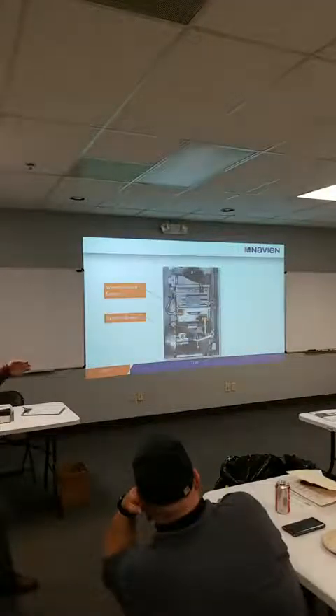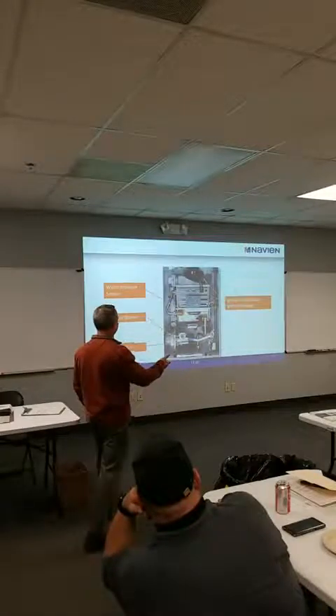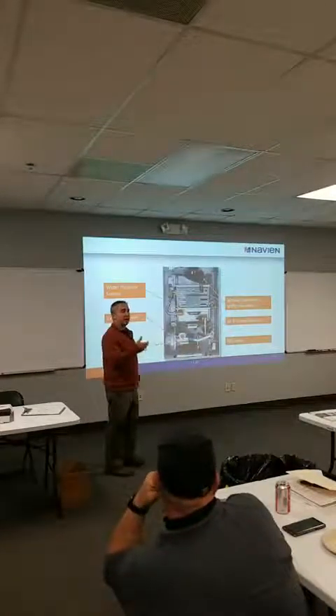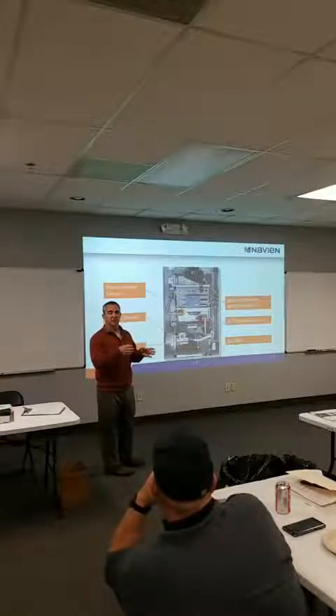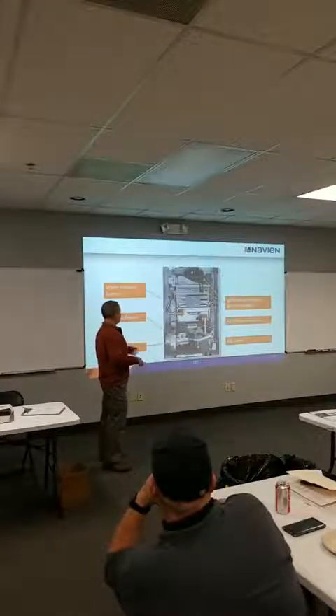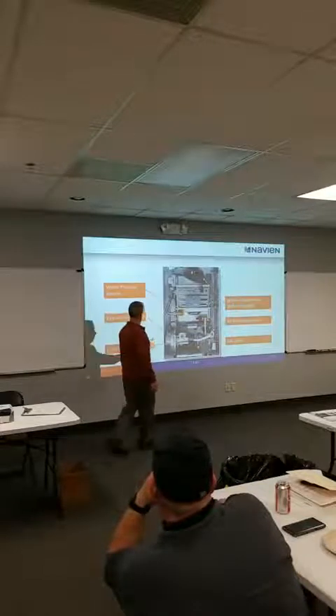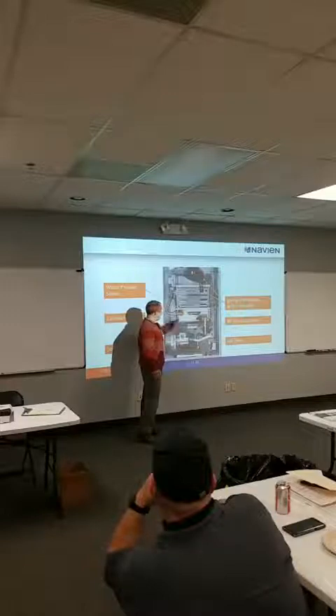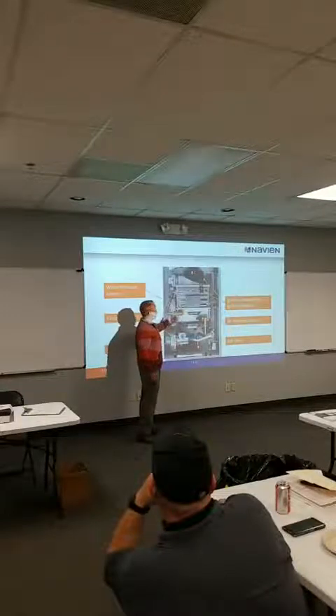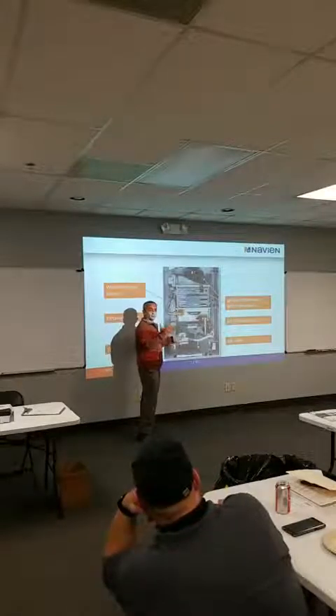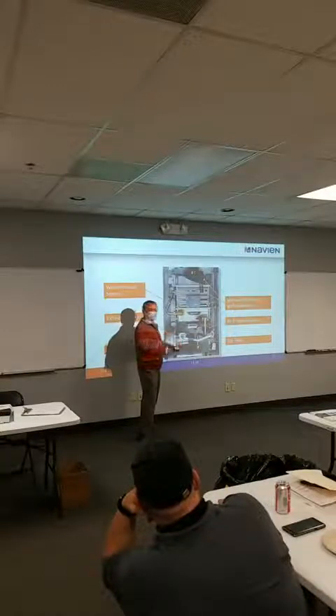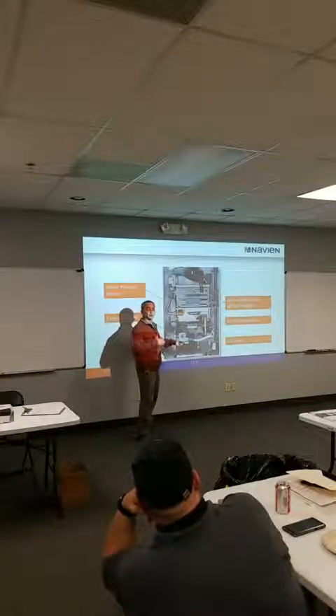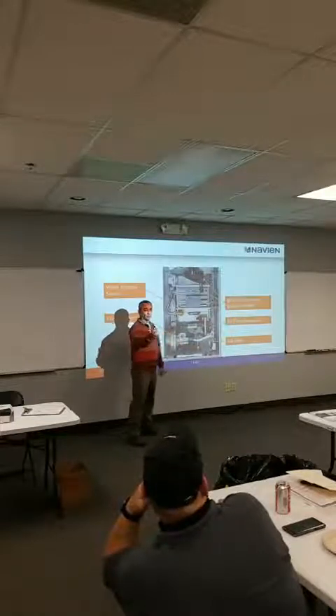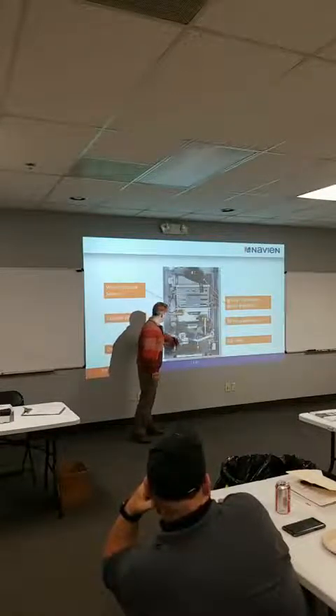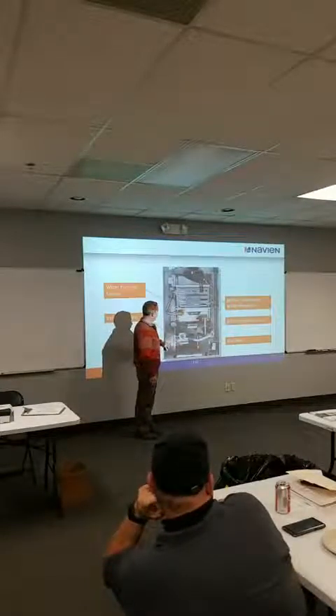The setup of all the equipment is going to be a little different, but the internal parts are basically the same. We just move them around based on either the heat exchanger that we're using or how much stuff we have to put in that box. So you're always going to have an inducer. You'll see our inducer draws air into the cabinet itself. When the cover's on, we're drawing air into the intake, which is protected by a screen. With the cover off, you're just drawing makeup air, which all of our units are approved for. So if you ever get to a job and the cover is off, anything that's in that cabinet or that room, we're actually drawing into the cabinet itself, into the inducer, and then into our burner assembly.